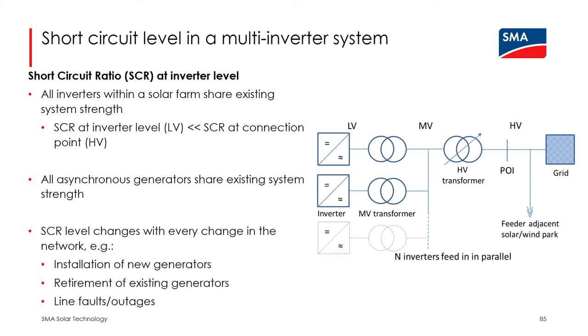So short circuit ratio is not a fixed number which is given during the installation process of a system, but can typically change a lot during the lifetime of a generator. This can be something that changes on a daily basis, for example, due to line faults or outages. But it also changes continuously, as I just mentioned, due to the additional installation or retirement of existing generators.